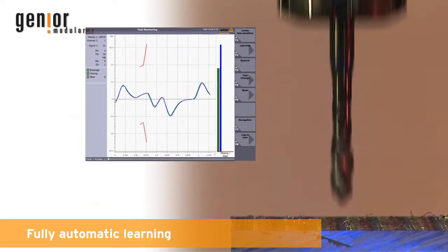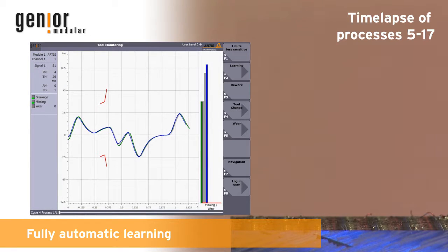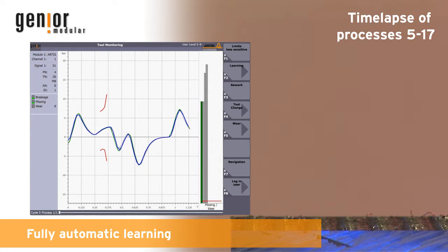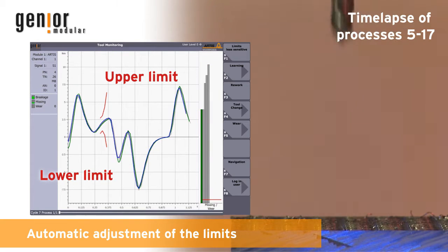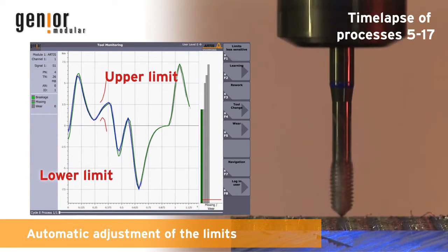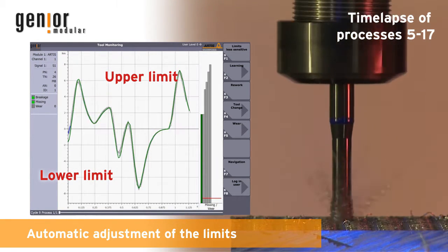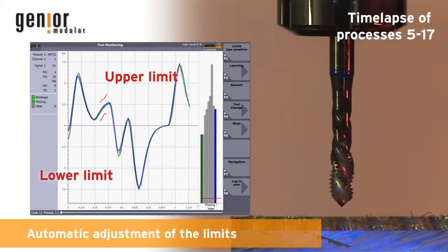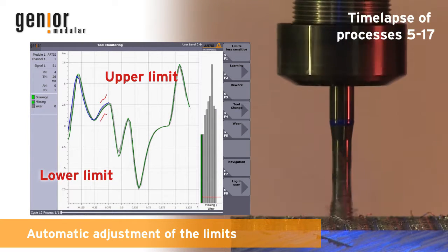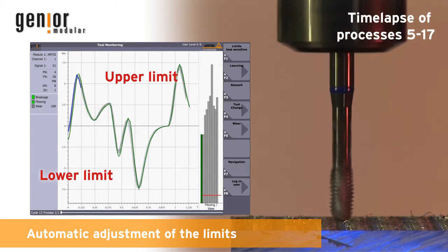Demonstration of the learning processes. The setting of the very first alarm limit is done automatically. During the following processes, these become more and more refined. After only a few processes, the monitoring is optimally adjusted and the system functions automatically without operator intervention. The last processes, displayed in grey, show process variations.